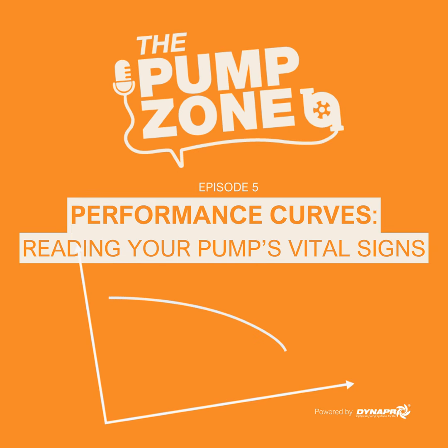Wait, hang on. If I open the valve completely to get maximum flow, that means less resistance. So wouldn't that make it easier? Could I actually overload the motor doing that? Well, yes, you absolutely could overload it because you're suddenly moving vastly more mass. As flow increases, pushing that massive volume of water per second requires way more physical energy. Oh, wow. So the power requirements just spike? They spike dramatically. And at the same time, your NPSHr goes up.